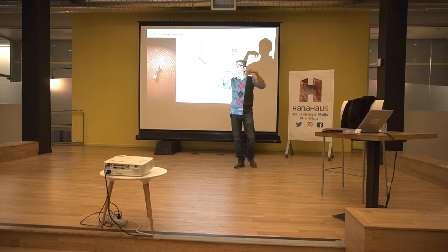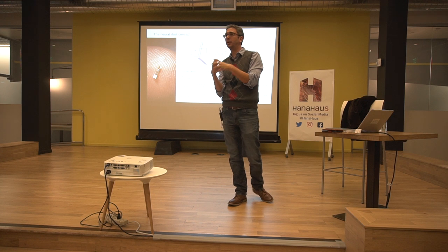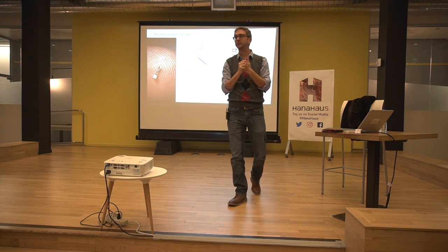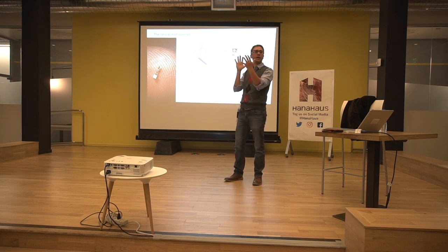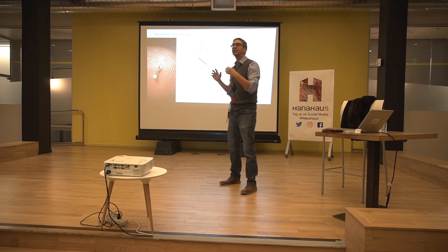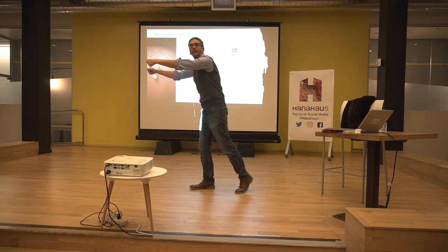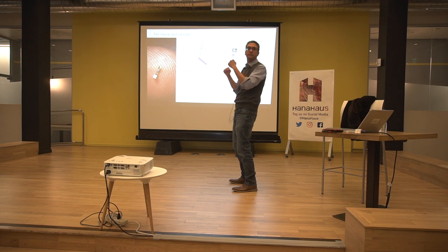Okay, so it's going to wash, it's just like my sound wave, it's going to hit the implant. Now what happens? Well, in my implant, I'm going to put a particular type of crystal called a piezo crystal. And when the sound hits the crystal, that crystal will compress and expand with the sound, by nanometers, I mean very small amounts, but it's going to do that. And the beauty of a piezo crystal is that it turns mechanical work into electrical work. So the piezo crystal, if I put electrodes on it, will now produce a current and a voltage at those electrodes as I, you know, torture it.